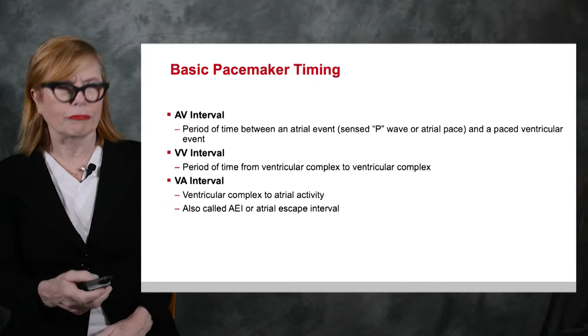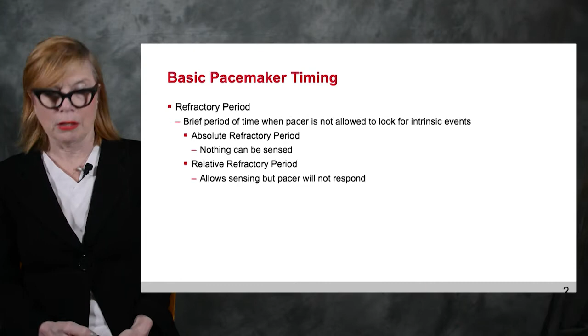Now, something else that is incredibly informative is that when we have sensing, what we also have is what's known as a refractory period. That refractory period is just like the refractory period endogenously. Endogenously, normally, the QRS to the midpoint of the T are absolutely refractory, and during that period of time, nothing can be sensed. The relative refractory period, which is from the downside of the T wave, allows sensing, but the pacemaker will not respond. It will not fire an impulse during that relative refractory period. If it did, you indeed would go into torsade de pointes from an impulse fired on the downside of your T wave.